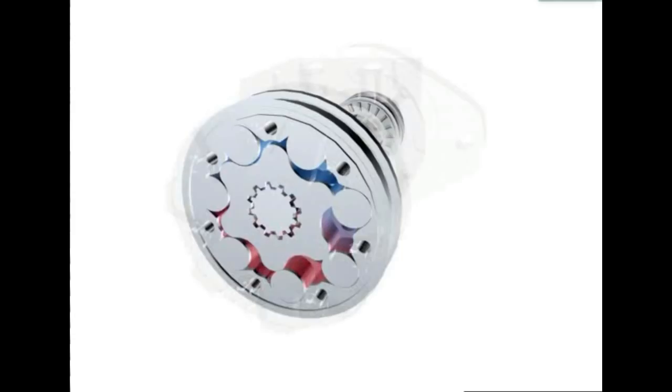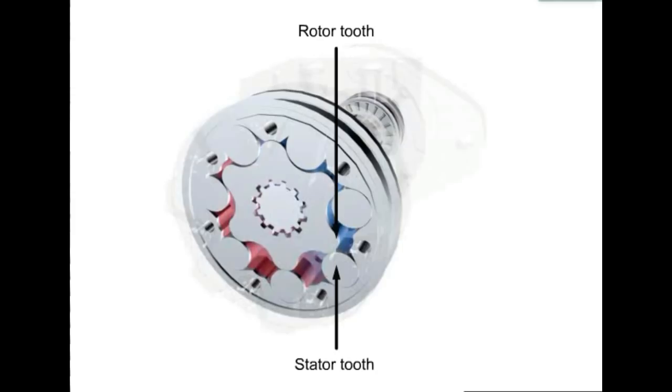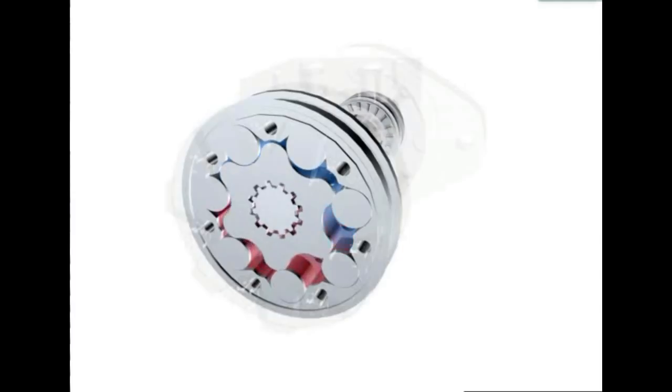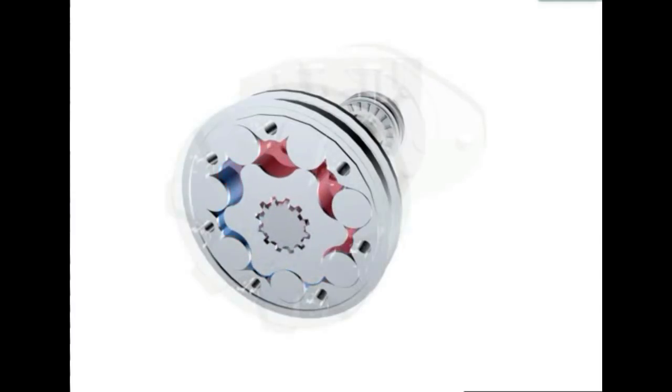Fluid on the opposite side of the cavity is forced through the rotary valve to the outlet port. As the rotor moves, the next rotor tooth and stator tooth oppose each other. The rotary valve allows fluid to enter the high pressure cavity in its new position, and the cycle begins again. These cycles cause the rotor to orbit around the inside of the stator.